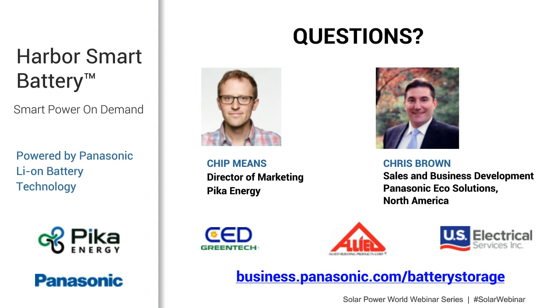All right, does this system have to use Panasonic solar panels, or can any type of solar panel be used? Unfortunately, any type of solar panel can be used. Well, I should not say any type of solar panel, but as long as it's compatible with the PV Link, which is the vast majority of modules out there. Certainly preferred by me. Yeah, the only modules you can't use with the PV Link are some of the legacy positively grounded modules, of which there are fewer and fewer out there. Pretty much anything works, but obviously Chris and I like it when you use the Panasonic modules with this, because that's just a good synergy for our companies.